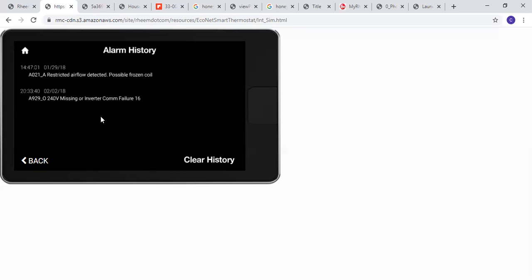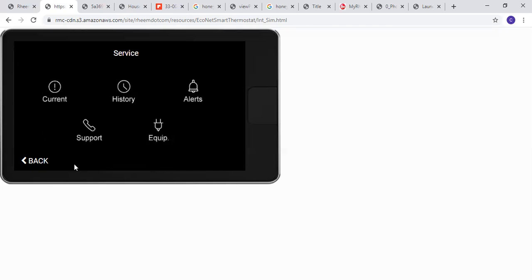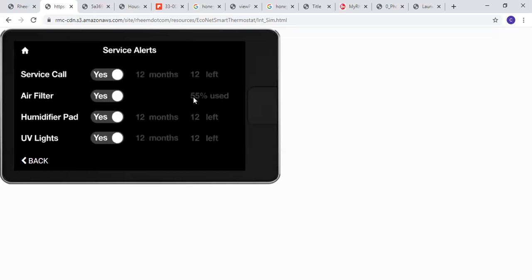We can go back and look at the history. So we had a restricted airflow detected, possible frozen coil, 240 volts missing. Probably somebody pulled the disconnect. And it will store 10 faults. It will kind of keep scrolling through there. So anytime you come up on one of these and you're even on a tune-up, check your history first, because it will give you a roadmap on what to look for.